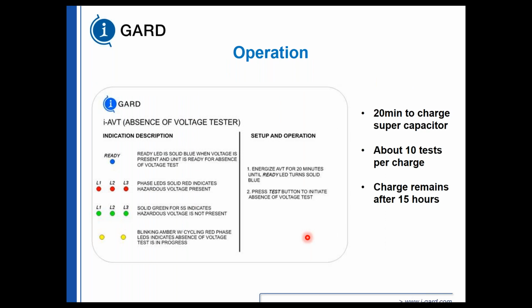So the operation is quite simple. The blue light comes on when the capacitor is fully charged and ready to conduct the test. The 3 red LEDs are on to indicate that there is a presence of voltage on the bus. We don't know what that voltage is. Well, all we know is it's more than 3 volts, but there's a voltage present on the bus. Because this 1 unit can verify the absence of voltage on circuits 120 volts to 690 volts, all we're telling you is that there is greater than a lethal voltage present on the bus.